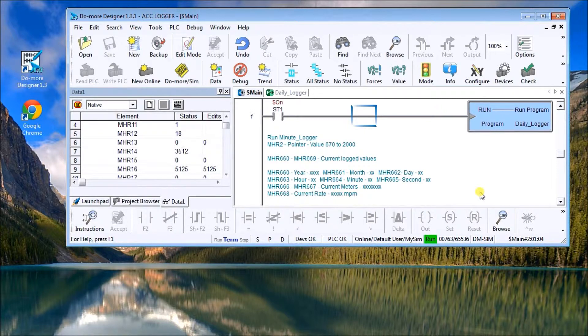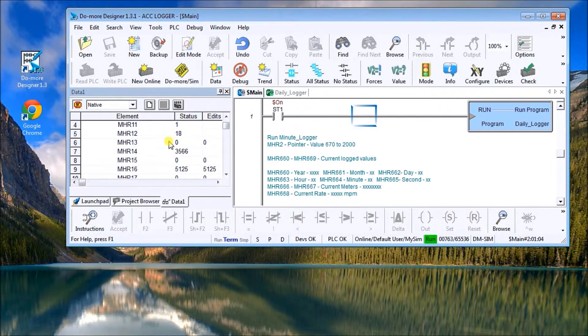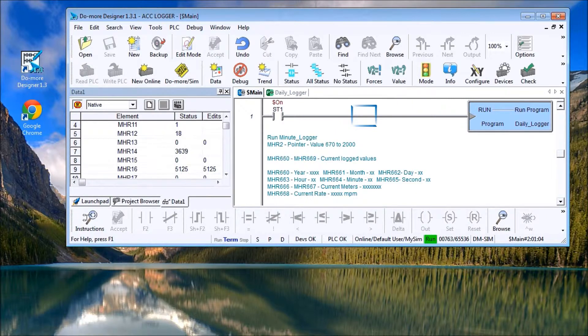What makes it robust is that the program uses indirect addressing in order to store data, so that if the communication link is broken, the information is stored within the PLC until the time that the computer can connect to it and grab that information back.